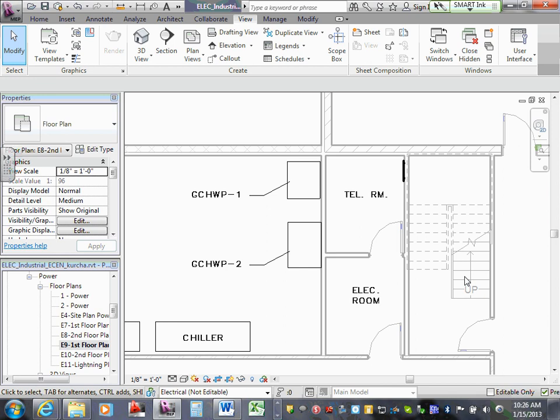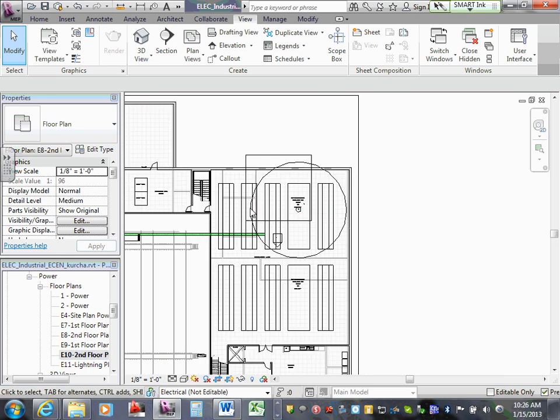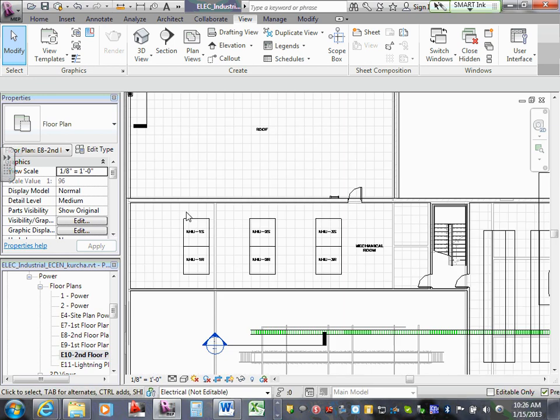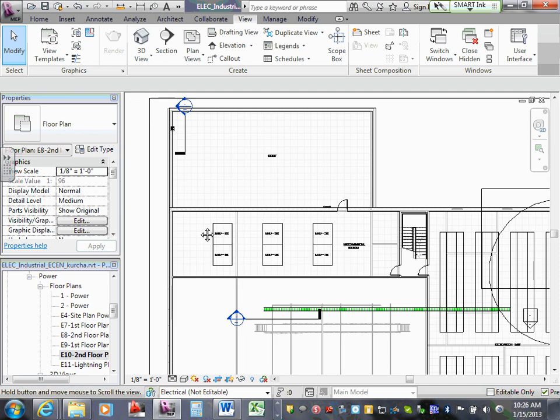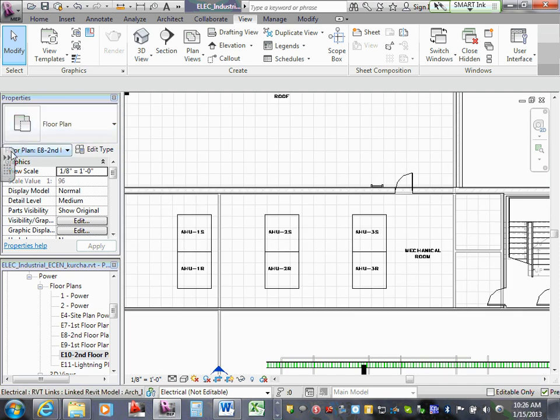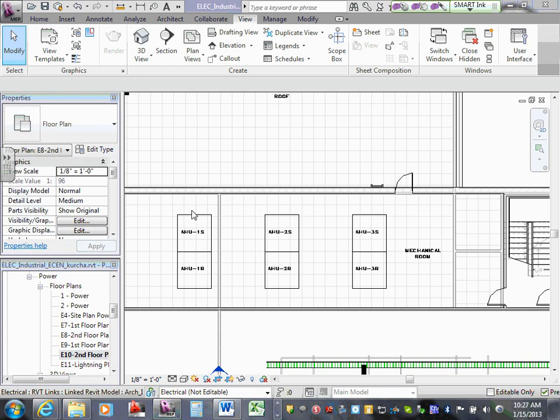Since we were talking about those air handling units earlier as well, should we look at that one? And the second floor, fun little fact is on the fire alarm code, duct smoke detectors are required on any air handling unit above 2,000 CFM. The fire alarm code requires for them to be on the return side. The mechanical code requires them to be on the supply side. So depending on which authority you're working with, is what they're gonna argue about. But typically, it used to be you had them on both supply and return. Now you just do it at supply side, have them on the return.